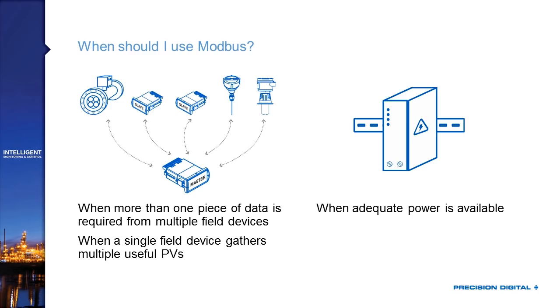In the case of multiple devices, you might use Modbus to read multiple level transmitters or all sorts of different sensors and devices around your process. One caveat is that Modbus requires power — it's really only applicable to systems where you have additional power available. If you're running in a low-power solar environment or mostly two-wire environment, Modbus probably isn't the right choice for that application.